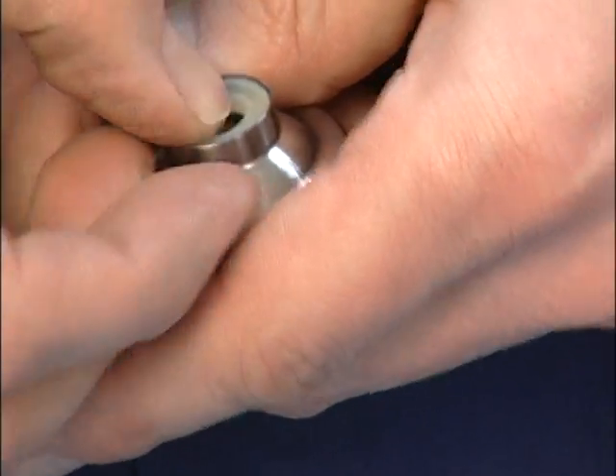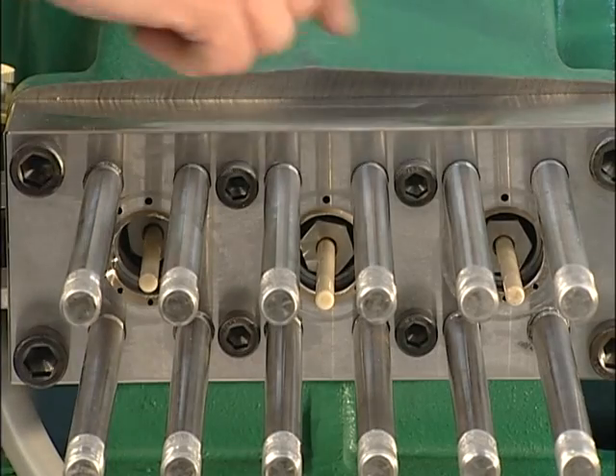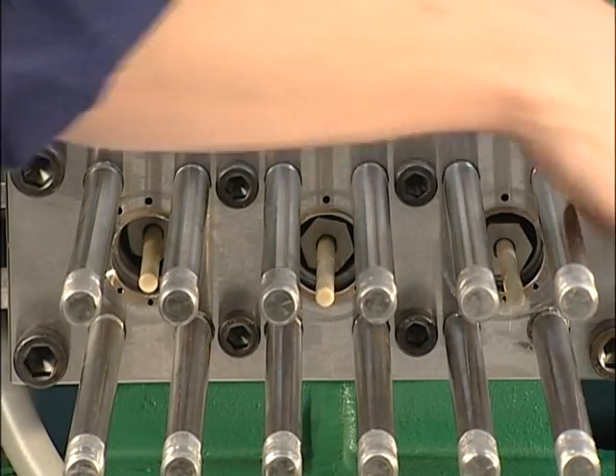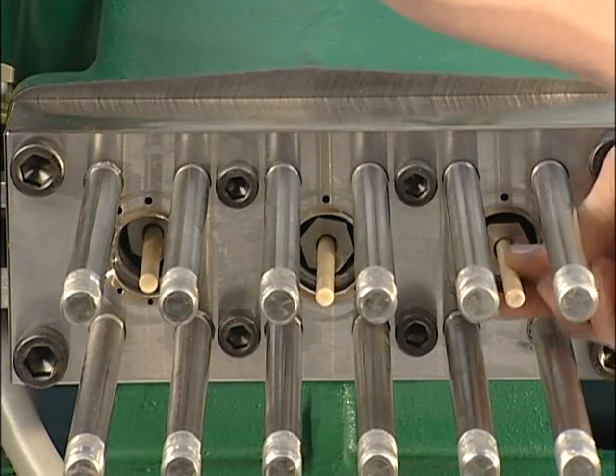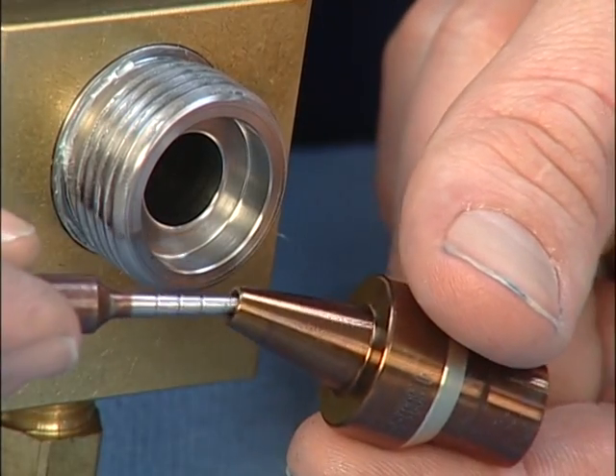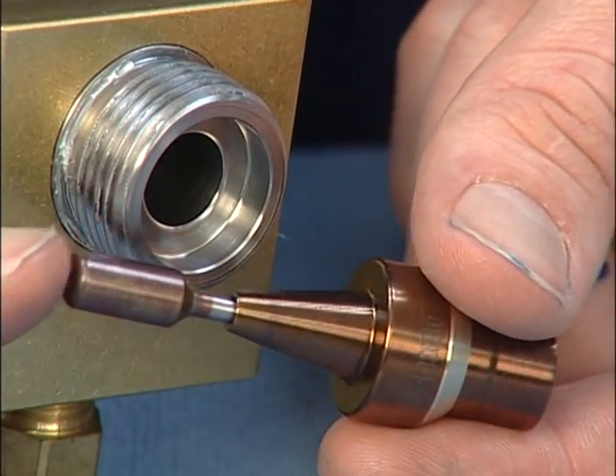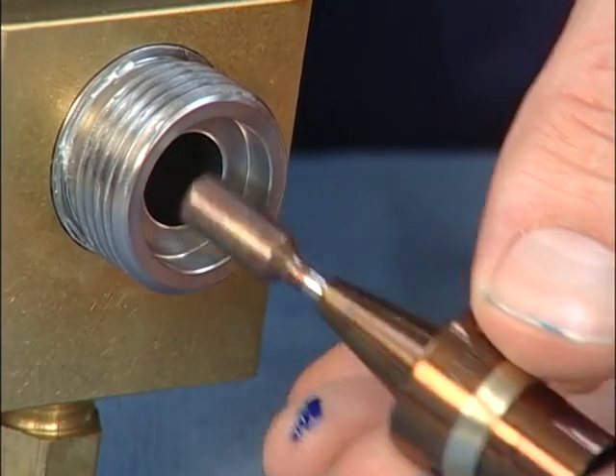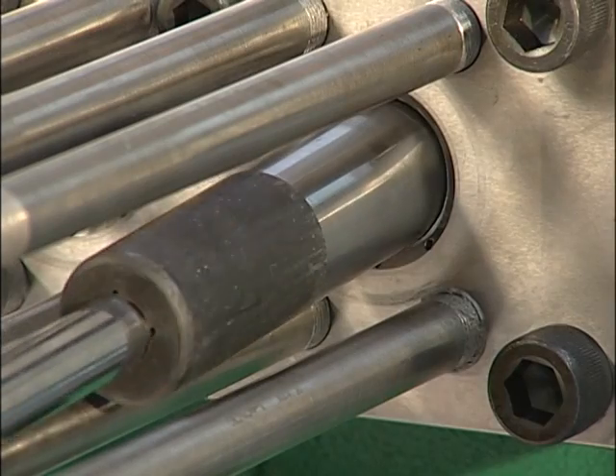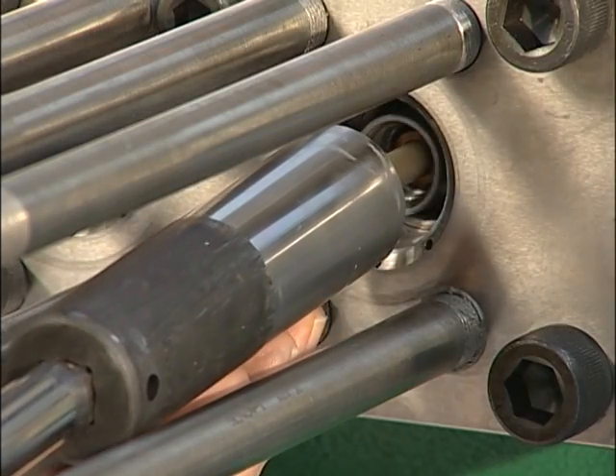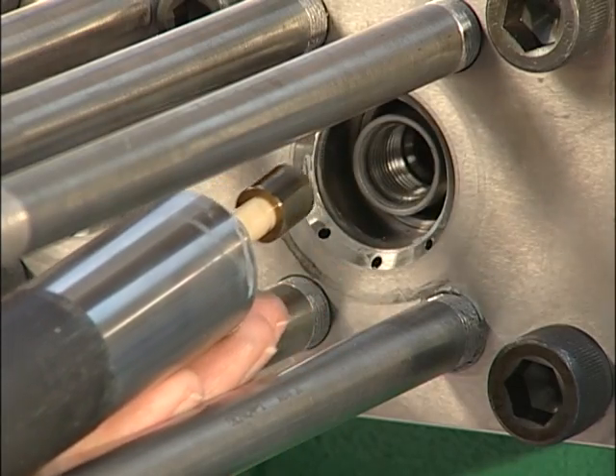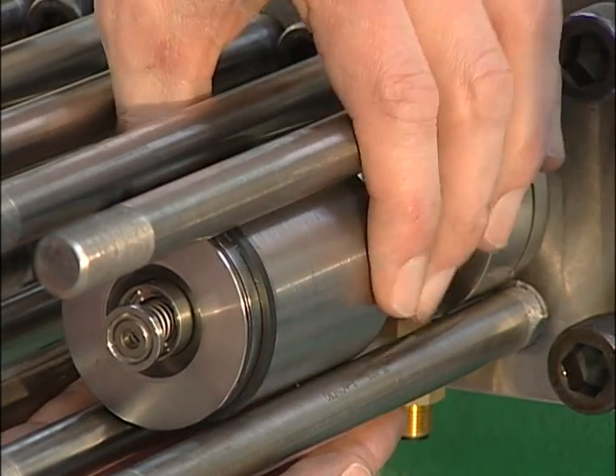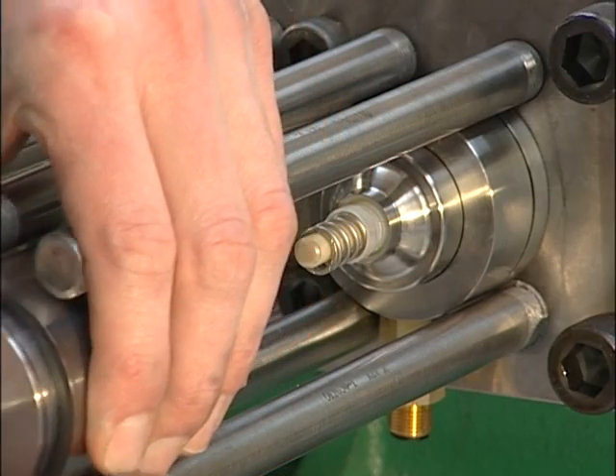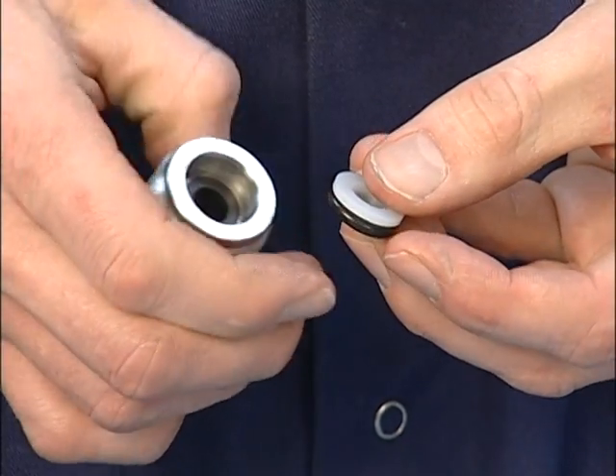For a 30 horsepower pump, the minor procedure is done every 700 hours, with a major service performed every 4 cycles, or 2,800 hours. Likewise, for the 50 horsepower pump, the minor procedure is done every 500 hours, with the major procedure done at 2,000, or every 4th interval. And for the 75 horsepower pump, it is every 300 hours for the minor and 1,200 hours for the major procedures.